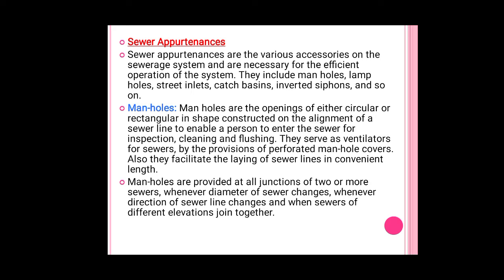They are ventilators for the sewage by provision of perforated manhole covers. Also they facilitate the laying of sewer lines in convenient lengths. These manholes are provided at all junctions of two or more sewers, whenever the diameter of the sewer changes, whenever the direction of the sewer line changes, and when sewers at different elevations are joined together.